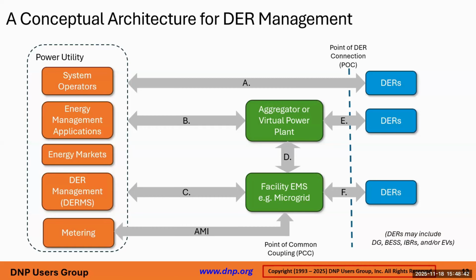Communications with utility-owned systems are often done using DNP or 61850. Utilities are already using these protocols for SCADA, so it's only natural that systems connecting to their SCADA environments support those same protocols. In some cases, Modbus may be used locally at the DER site, which requires conversion through some form of local DER gateway—at least that's commonly what we see.